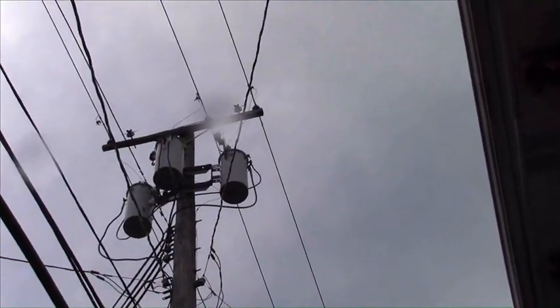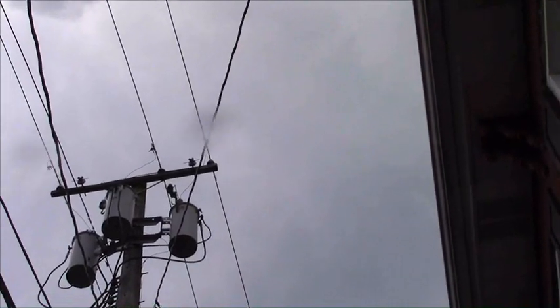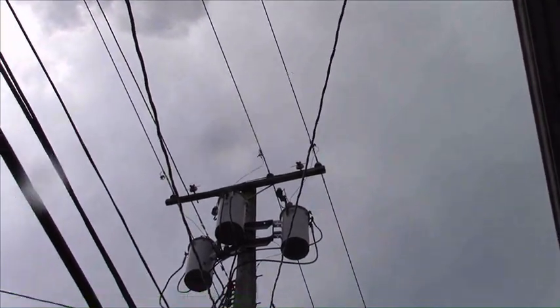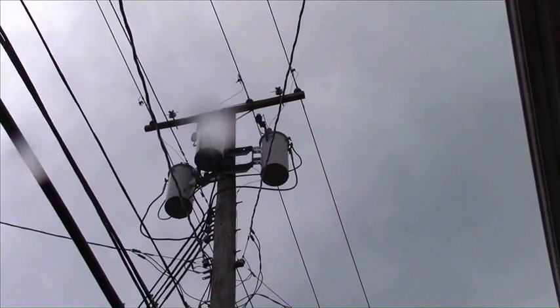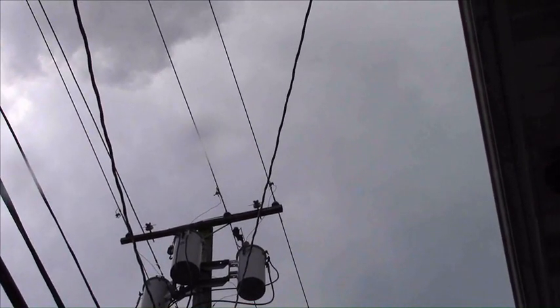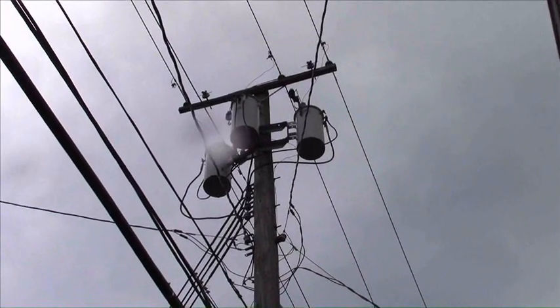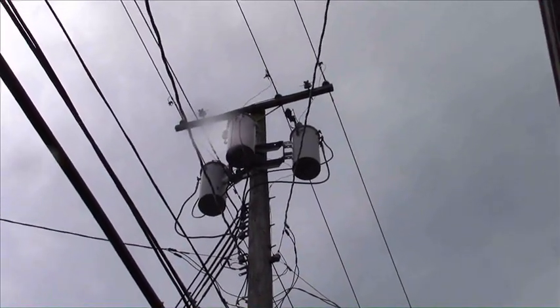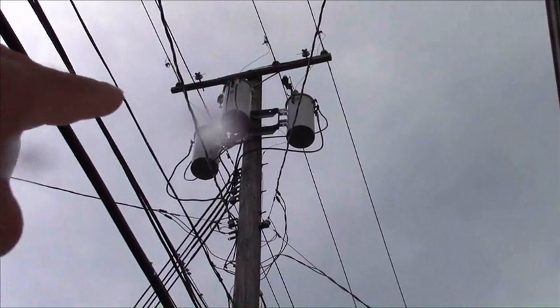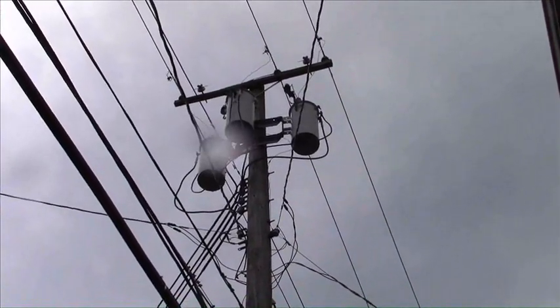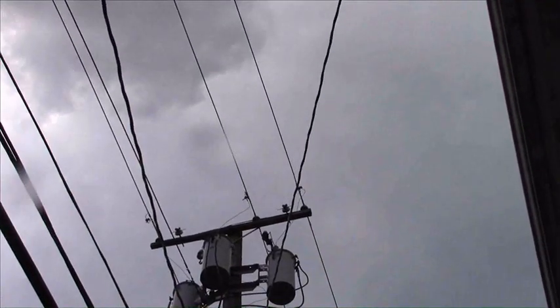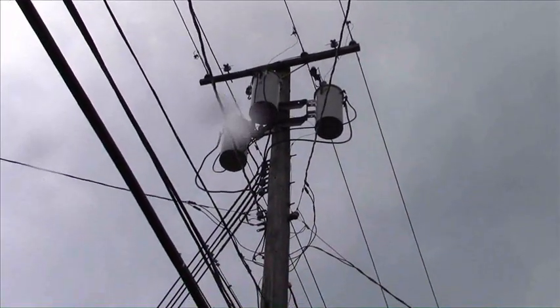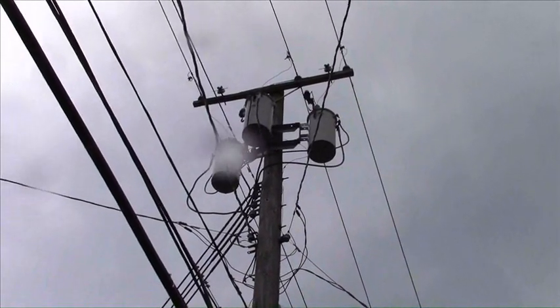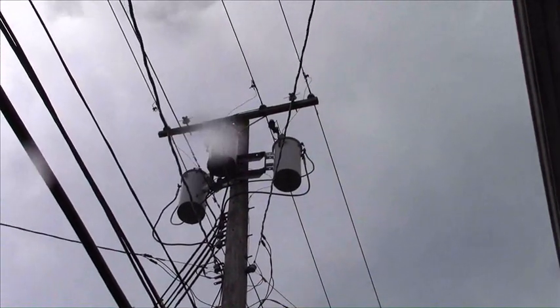So there's a delta configuration and there's a Y configuration. One provides commonly 277 volts, one provides 208 volts, and a transformer in the building taps off 120 volts to normal equipment that needs to be powered. But that's a 3-phase system right there, and if you can see on that center transformer, there's a 25 on there. So each transformer has 25 kilowatts capacity. That's a 3-phase power system, which residential houses do not have. This is shopping malls, industry.